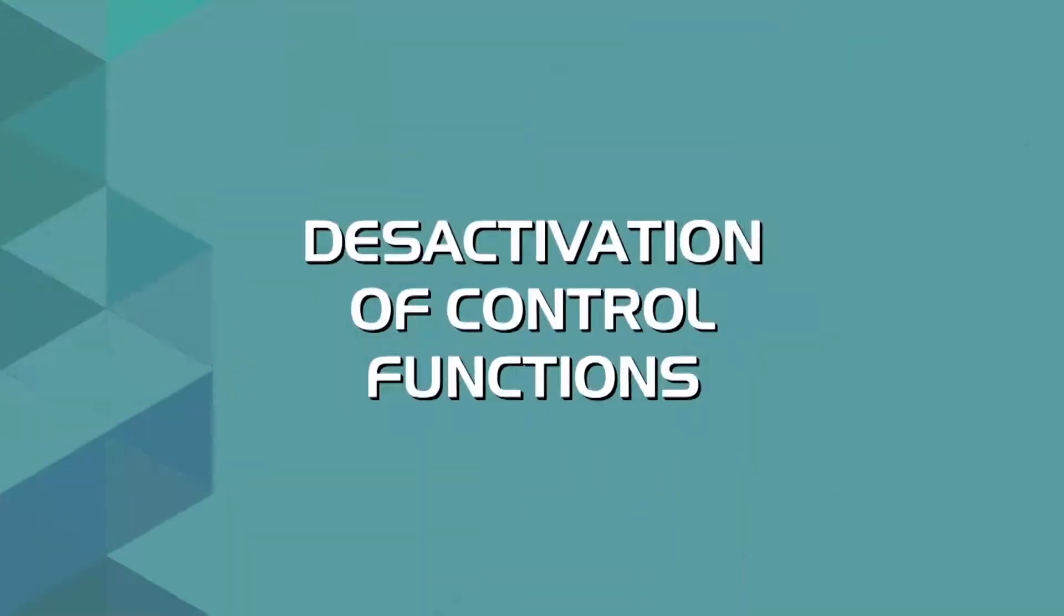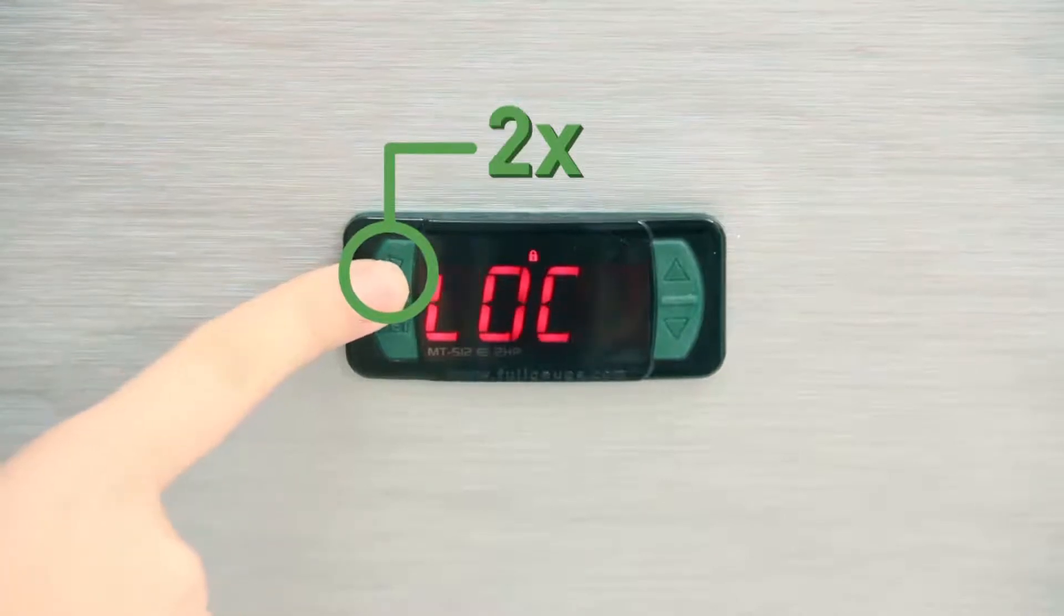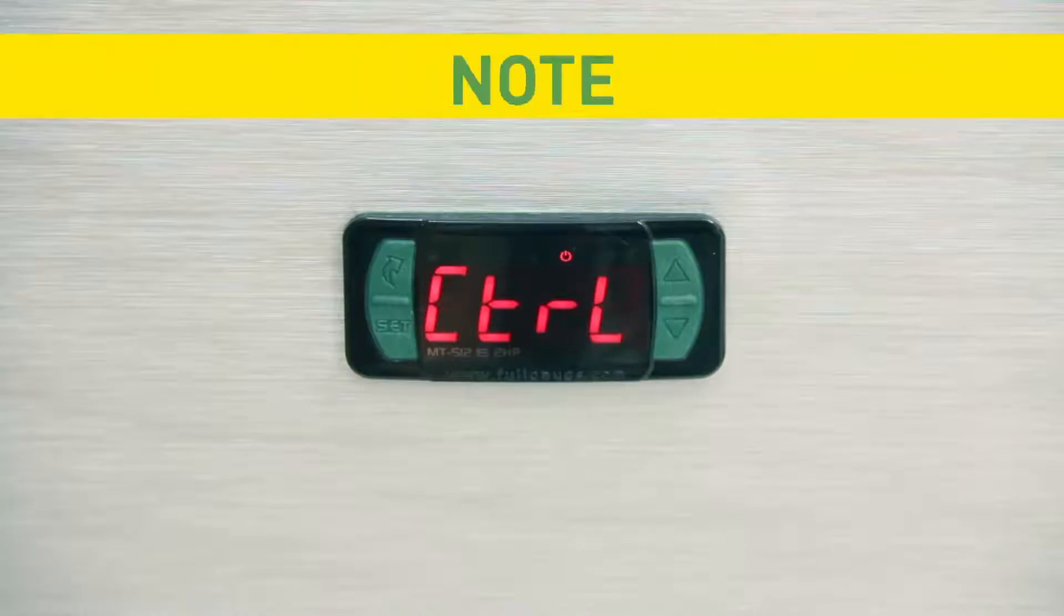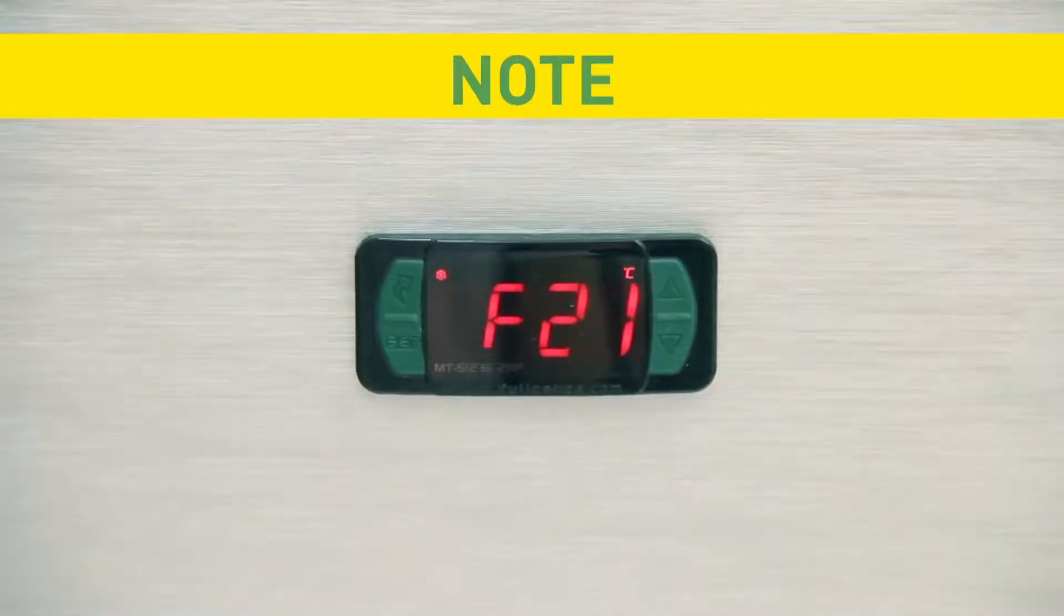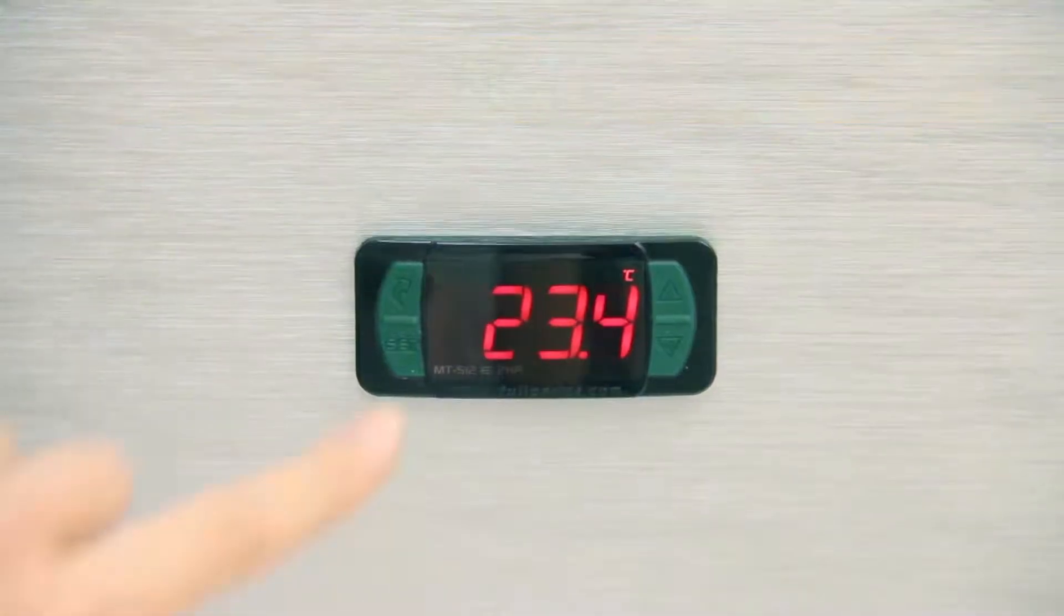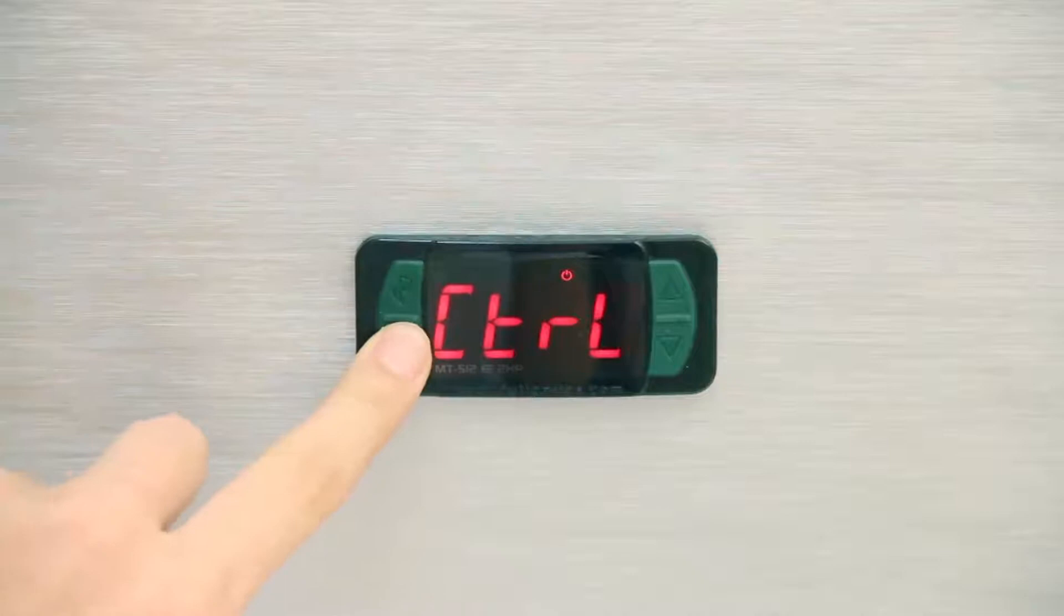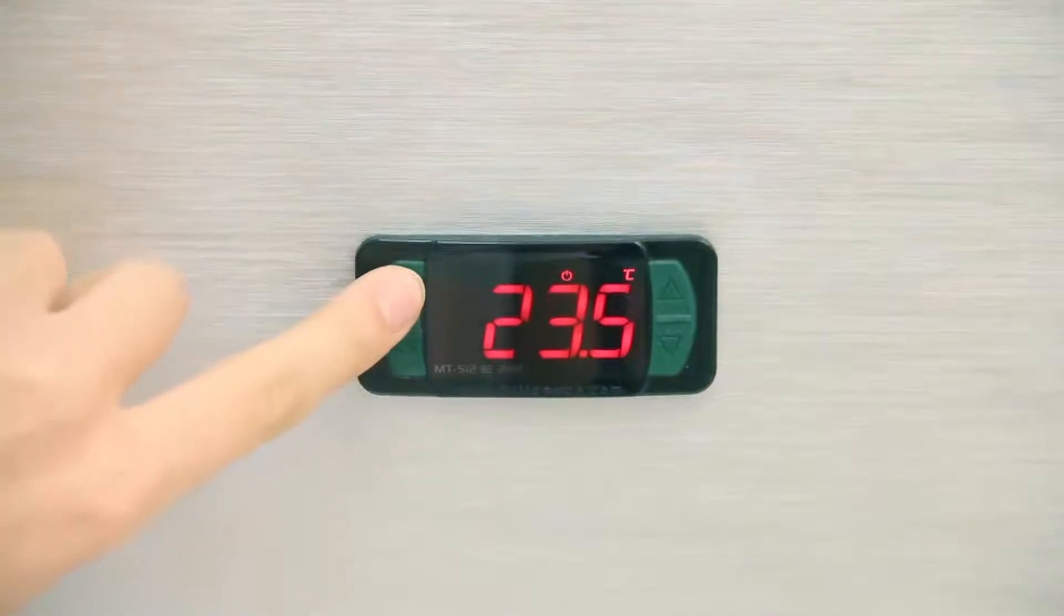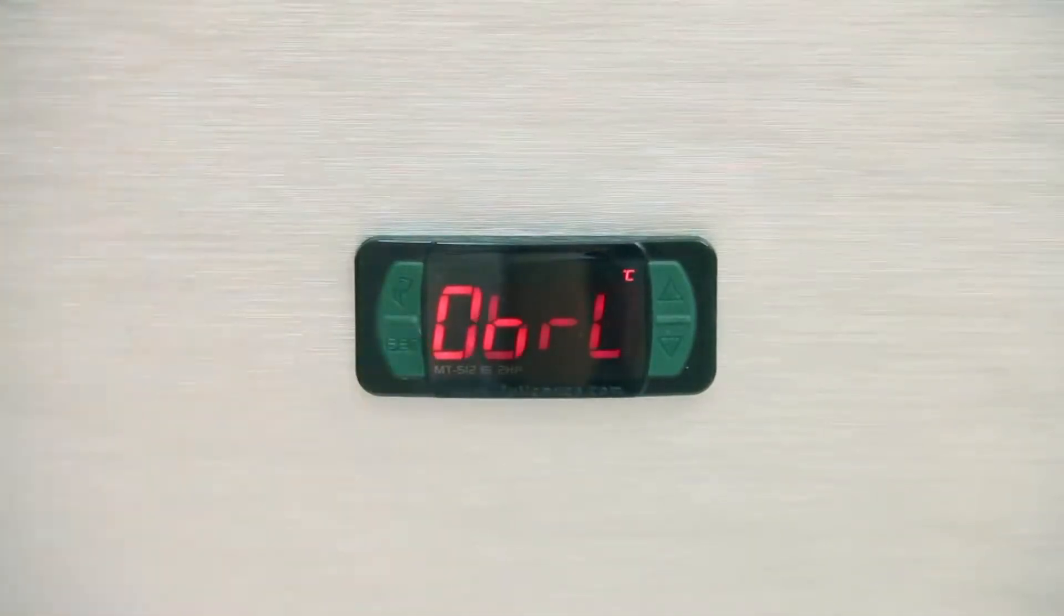Deactivation of control functions: This function causes the controller to operate only as a temperature indicator, turning off the load control relay. Note: to access this function, set the F21 parameter as explained in the user's manual. Through the FlatTech key, access control, then press set. The display alternates between temperature and the disabling indication. To reactivate the control functions, apply the same procedure, which will cause the reverse effect.